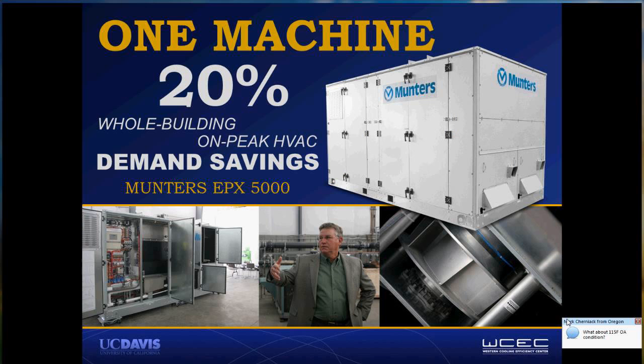Okay, so in conclusion with the Munter system, we took all this performance data and mapped it into a scenario comparison where we thought of it being added onto an existing big box store to offset all of the ventilation requirements. So just as with the Coolerado and Climate Wizard, the unit almost always covers all of the ventilation cooling load, and most of the time also provides some room cooling. So all of the existing rooftop units can operate in an auto mode where they only have to turn on to circulate air when there's a call for cooling in their zone, which can save a considerable amount of annual fan energy.